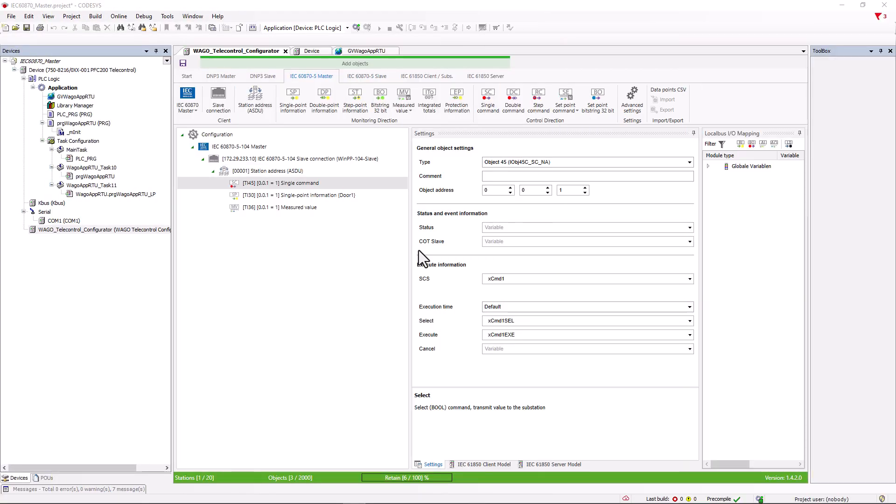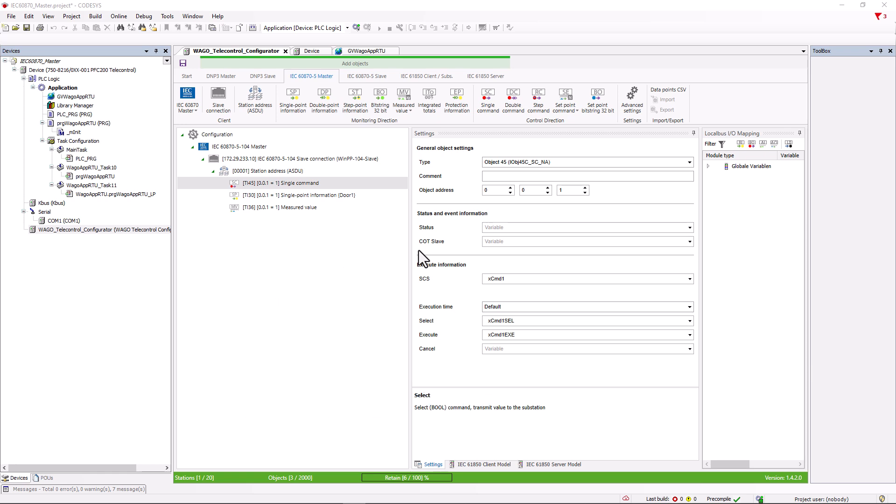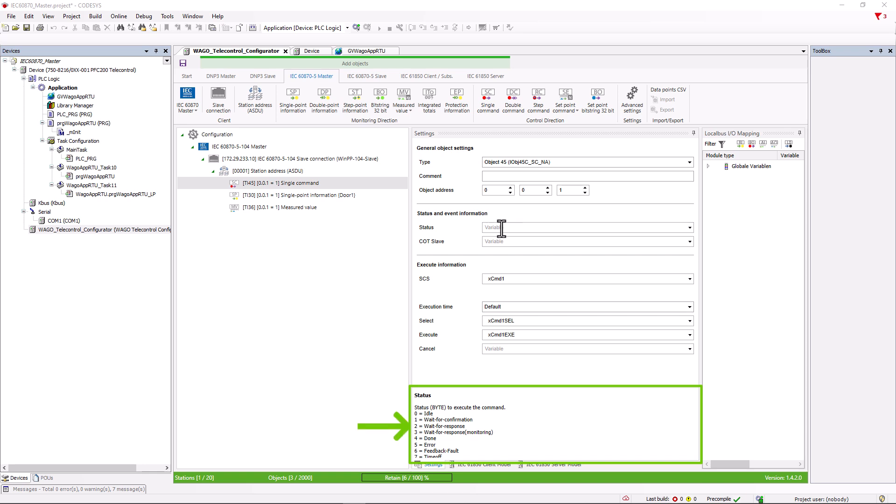For commands, the master expects feedback from the slave that the command has been executed. This procedure is defined, the command is sent by the master with activation COT6, the slave confirms receipt with confirmation COT7, the slave sends the field level feedback that the command has been successfully executed with COT11 and terminates the command with activation termination COT10. In the status and event information area, we can create a byte variable to analyze where we are in the process. If the command is successfully transmitted, the variable will increment from 0, idle, to 4, done.